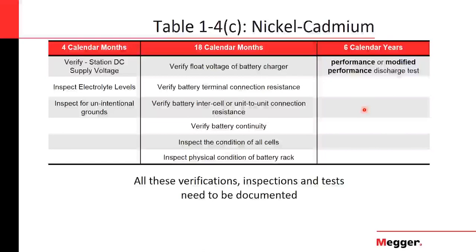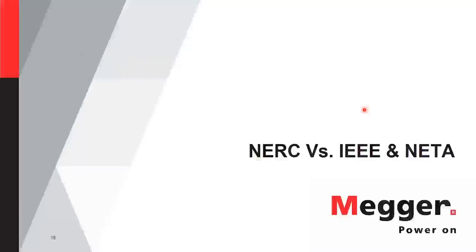So really it's not a very good indicator of the condition of the battery, so that's the reason it is not included in this table. As I mentioned, there are more tables. There are other tables, D, E, and F, and table 3, but those are mainly for DC systems that don't have batteries, or that just ask for a basic voltage measurement at the protection system. So they don't really focus on the batteries per se, but more on the DC system.